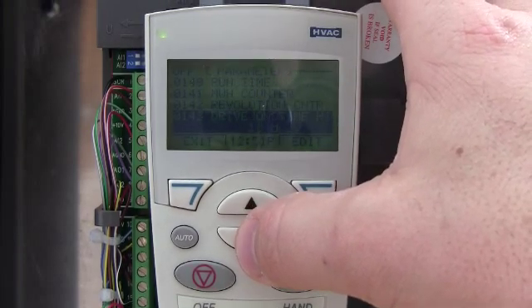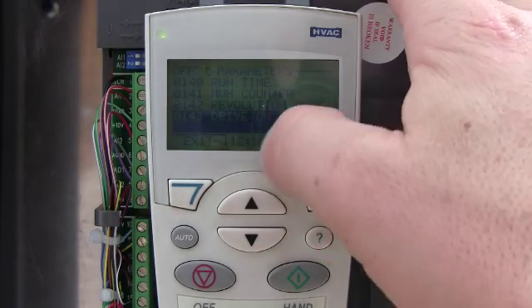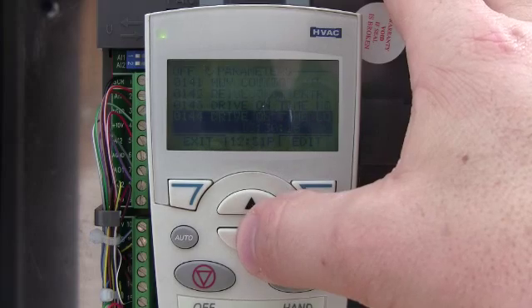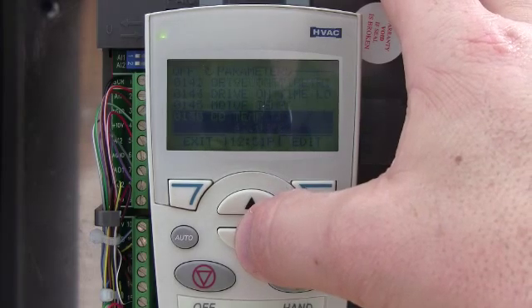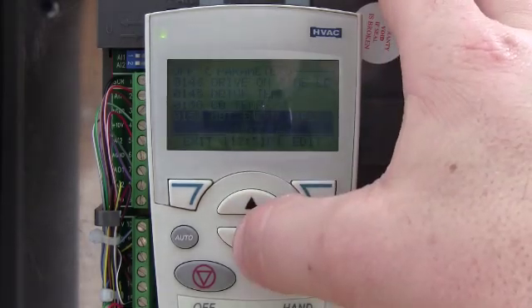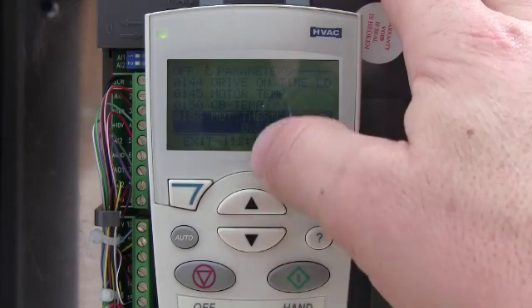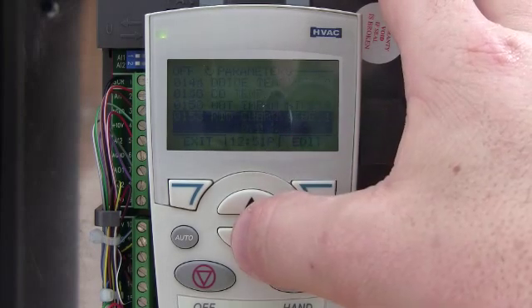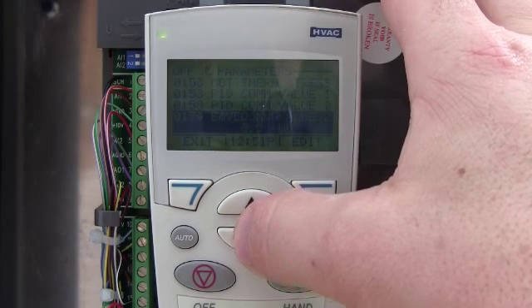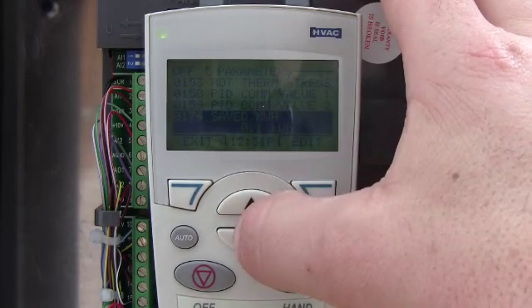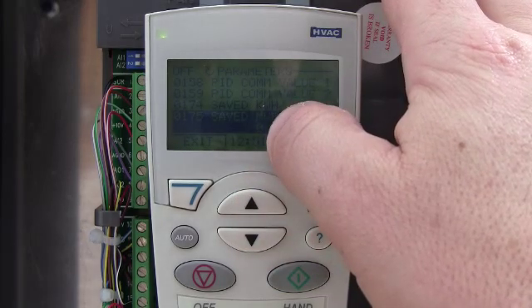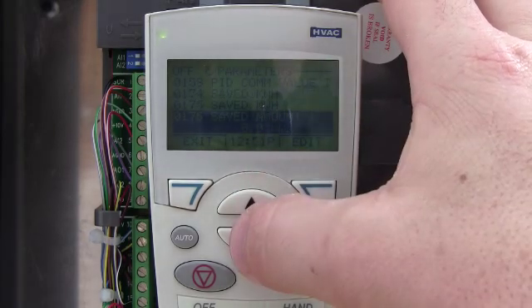A lot of this stuff — revolution counter, drive on time, 11 days, drive on time in hours. Motor temperature — that's calculated. CB temp, that's control board temperature. Motor thermal stress in percent. PID com value one and two. Save KWH — that's if you wanted to reset it and kind of trend it to see what it's doing month to month. Some people do that.